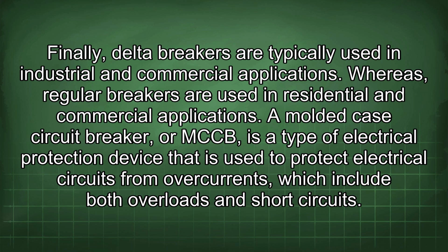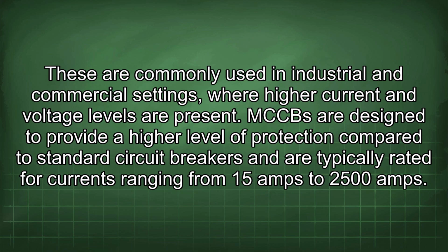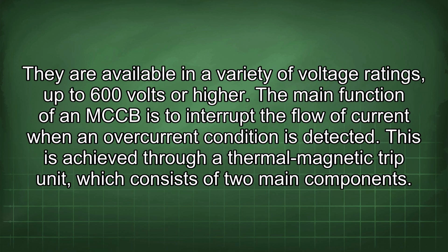electrical circuits from overcurrents, which include both overloads and short circuits. These are commonly used in industrial and commercial settings where high current and voltage levels are present. MCCBs are designed to provide a higher level of protection compared to standard circuit breakers and are typically rated for currents ranging from 15 amps to 2500 amps. They are available in a variety of voltage ratings, up to 600 volts or higher.